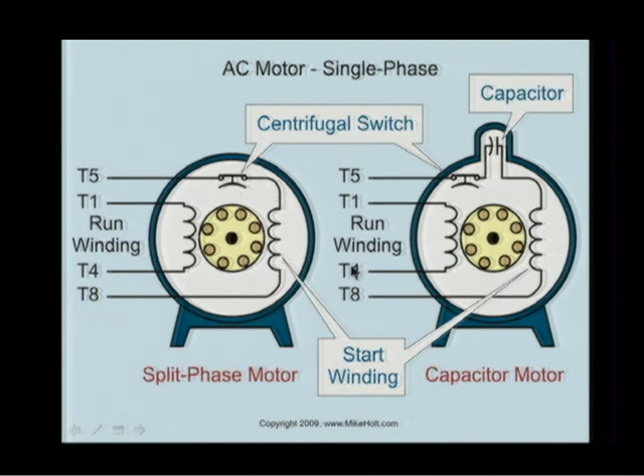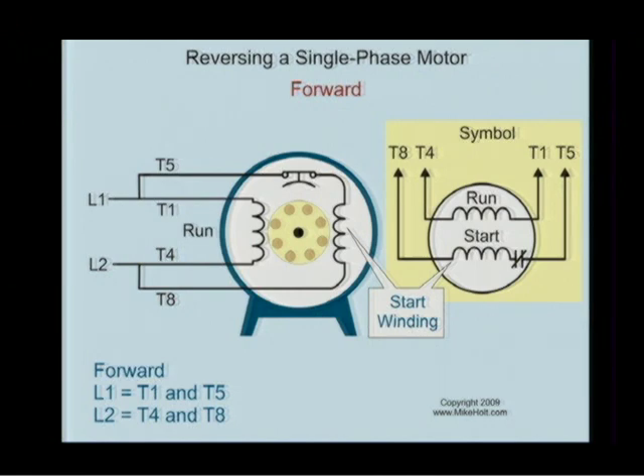Okay, not more to talk about that right now. Let's see how this works out. Now, Steve, you seem to be familiar with this. Are they marked as a run winding and a start winding? Is that how they're shown on it? Typically what you'll find on the nameplate is that it just shows you the connections. It says this is wired for the low voltage, so it'll say for 120, connect T1 and T5 to line 1, T4 and T8 to line 2, and then it'll say to reverse, interchange leads 5 and 8. So that's how you know which one is the start winding, by that nomenclature. Okay, it tells you which ones to reverse, which are your start leads.